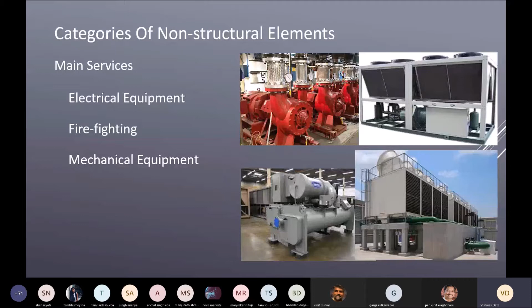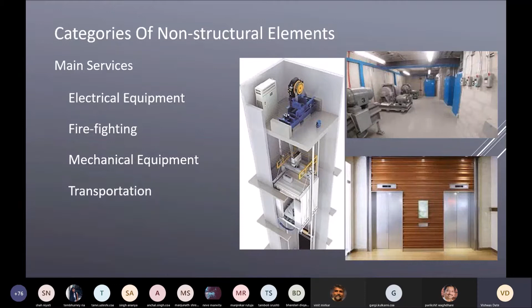Then the third thing will be transportation. Lifts will be the most important factor post earthquake. During an earthquake, lifts may be automatically shut down. They should not be working anyway, because under vibrating conditions the lift will not work properly. But it has been found many a time that the guide rails come out during an earthquake because they are not considered a very strong structural necessity. They are generally provided properly, but perhaps not adequately supported in the lateral direction. Or your motor, which is in the lift machine room, or even if it's a machine roomless lift, that support has to be sturdy enough to keep the motor working.